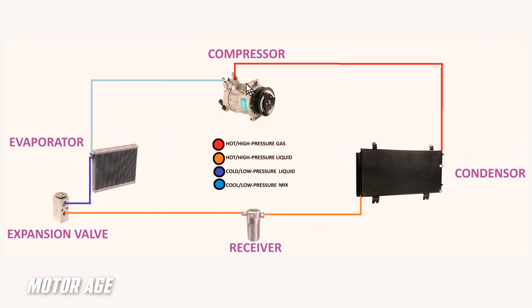Again, this is nothing more than a generic drawing of an orifice tube system. And just for good measure, I will show a picture of an expansion valve system. The process is very similar, but the configuration is a bit different. So instead of having a fixed restriction here, we have a variable restriction here. And this is usually coupled with a variable displacement compressor in many configurations.